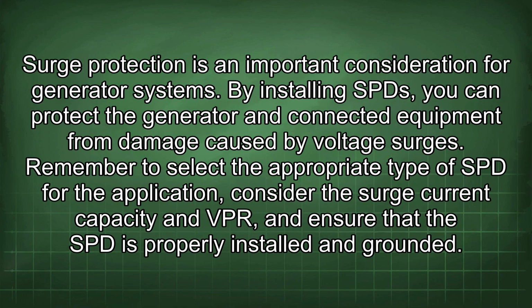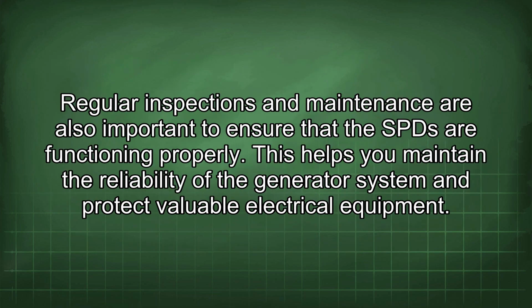Surge protection is an important consideration for generator systems. By installing SPD, you can protect the generator and connected equipment from damage caused by voltage surges. Remember to select the appropriate type of SPD for the application, consider the surge current capacity and VPR, and ensure that the SPD is properly installed and grounded. Regular inspections and maintenance are also important to ensure that the SPD are functioning properly. This helps you maintain the reliability of the generator system and protect valuable electrical equipment.